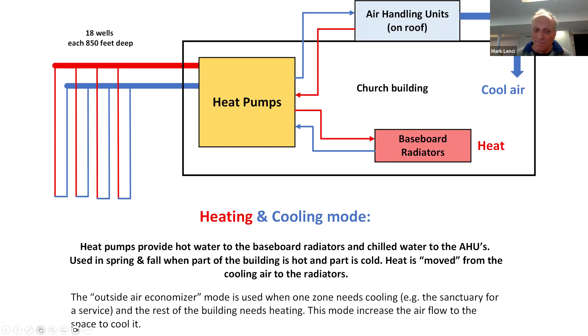In the spring, that south side gets the direct low angle sun and it gets hot, and the north side doesn't get any and it's cold and has to be heated. So what happens is the side that's hot, you're going to cool with air, which is going to warm that loop water up. We send it right to the radiators on the other side and heat those rooms. So we're actually moving the heat from one side of the building to the other without the use of heat pumps. And we supplement them with the heat pumps as is needed to add or subtract heat or cooling, depending which side's hotter and colder. So that's kind of a really interesting feature of this.